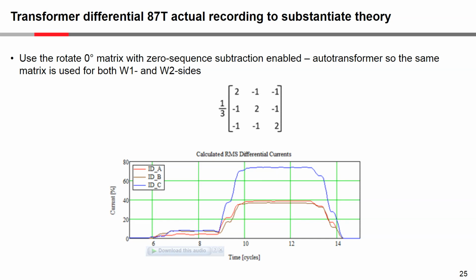If we take the 0-degree matrix, and this is essentially the matrix that would make a Y winding the phase reference, okay, and because it's an auto transformer with a delta tertiary, we have to use the form that subtracts the 0 sequence. But now you can see we get the highest differential current in the faulted phase, which is phase C. We get half the current in phases A and B. And if you look at the magnitude of phase C, you can see it sits somewhere just 75 or something on that percentage line. And so you can see that the differential current in phase C here was actually a little bit bigger than what was measured when we got the 2 equal differential currents using a matrix that would effectively be the same as using the delta side as the phase reference.